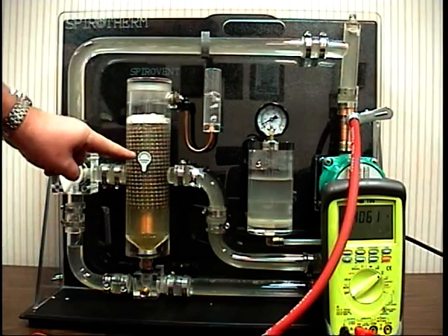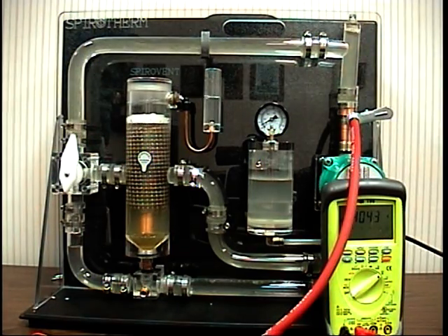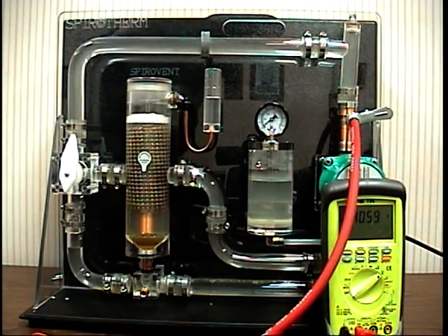You can see the dirt falling out, micro air bubbles coming up through the Spirotherm air vent. And very quickly we're taking most of the air, as far as the free air, out of the system. Most of the entrained air. It's not going to do it all on the first pass. It will take several passes in order to do that.